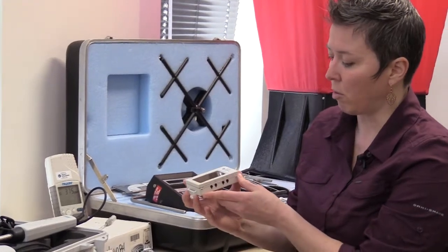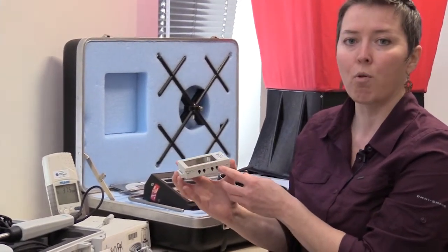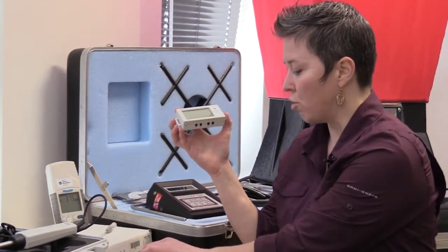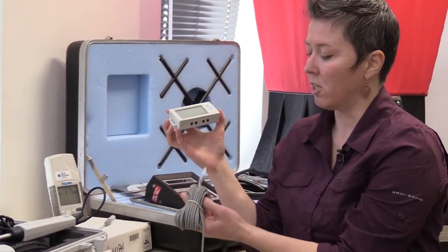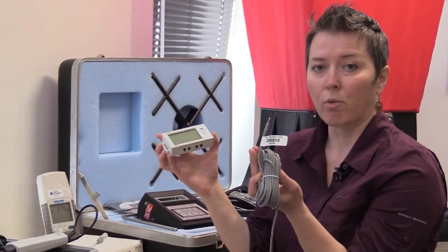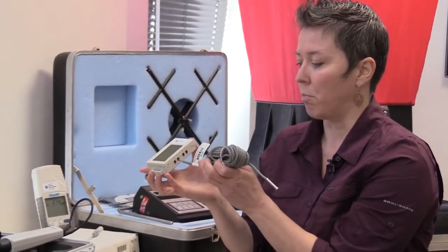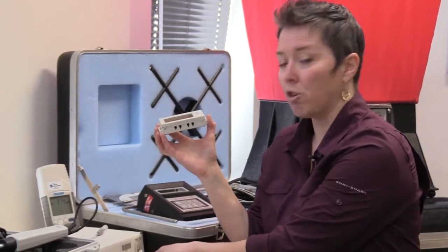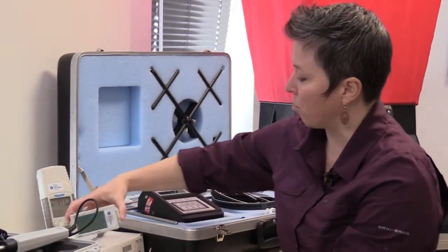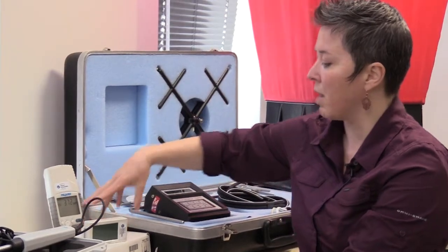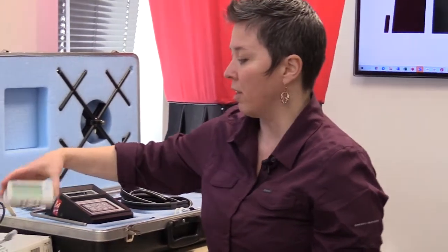Now, what's versatile about this is then you have 3 additional ports on this 4-channel logger, so you can configure those to measure other things, such as temperature. This is a temperature and relative humidity sensor. So this could plug into another port, and you could get those measurements if those are useful to see how well your system is maintaining temperature while bringing in all of that outside air. You can also use the 4-channel logger with CTs or current transducers to log power consumption. So very versatile system there.